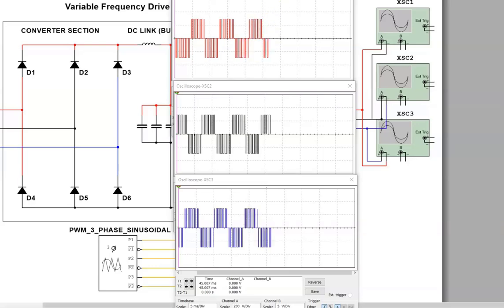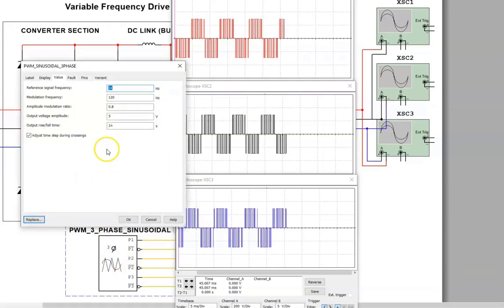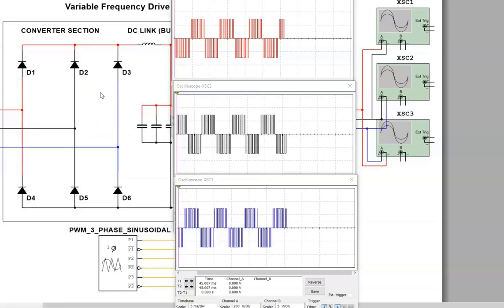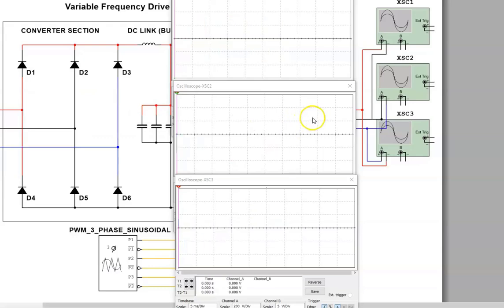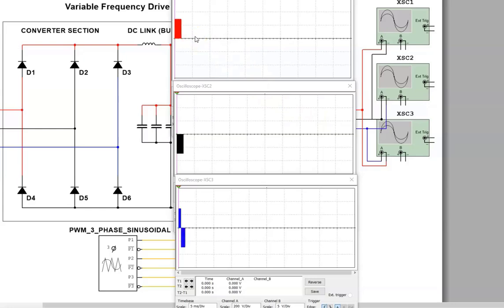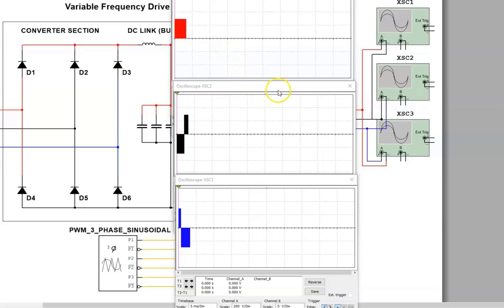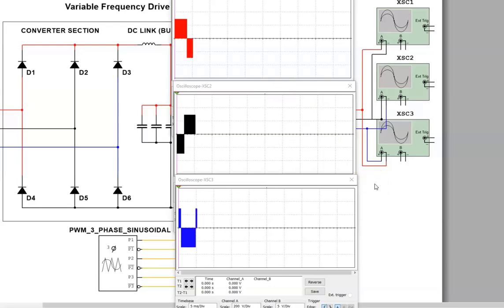What I'll do now is I'll just take that up to 16 kilohertz. I think it's going to slow down the simulation quite a bit. It's a lot of work for it. Each one of those is turning on and off 16,000 times a second to create that AC. So when you set the carrier frequency on an inverter drive to 16 kilohertz, it's basically what you're seeing at the output. Very, very fast switching. It's actually harder on the drive.